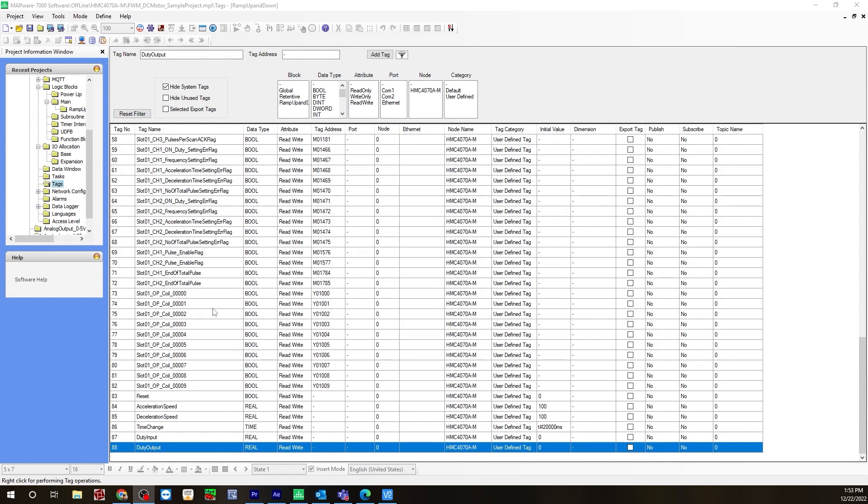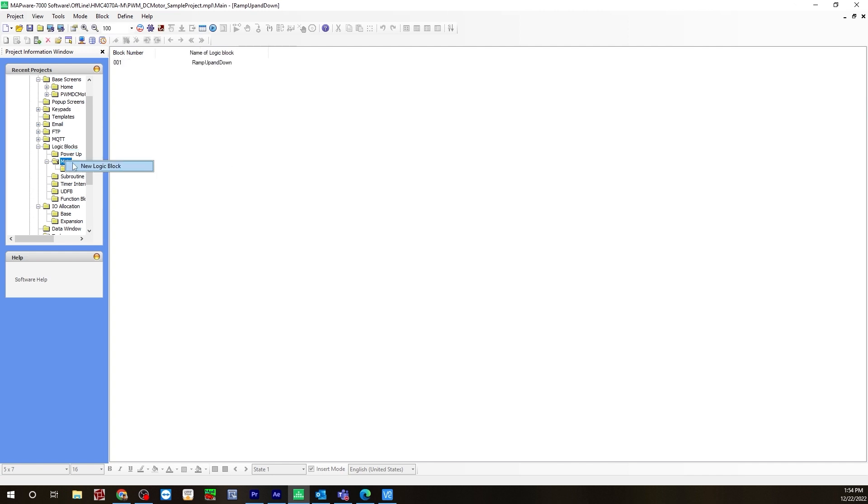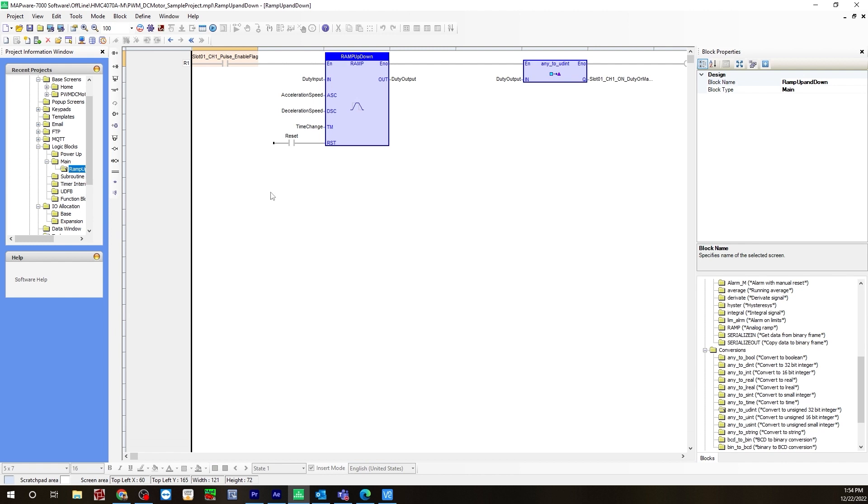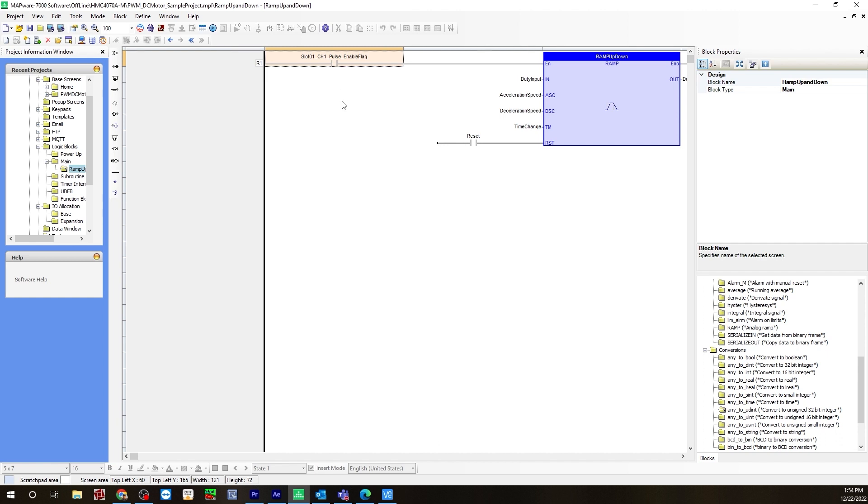After you create the tags, you'll next create the logic blocks. Go to the logic blocks folder. Under main, you would right click, select new logic block, and I've named it ramp up and down. To add logic blocks, you would first insert new rung, and the first piece of logic I have is an input coil. I'm using a register that is created when you configure your IO, and that is the pulse enable flag. You need to put this in your logic to enable pulse width modulation. That's slot one channel one pulse enable flag. That goes first in your logic.